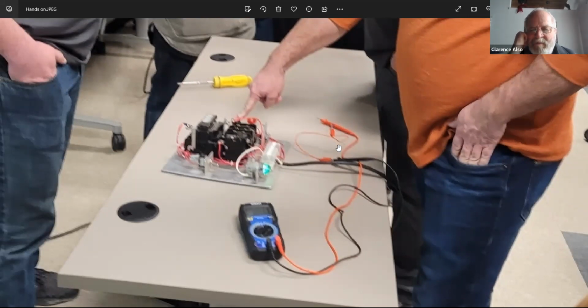Because it's an alternating current, it doesn't matter if on your meter you use your black probe to ground, or common, or otherwise. Here, basically, he was going to use his black one, and his black one should have been tied to some place. On those terminal strips, where that black cord goes into, there's a neutral, there's a number 2, the low side of the circuit. So when he's doing his troubleshooting, he's got to be putting his lead on number 2 on that terminal.